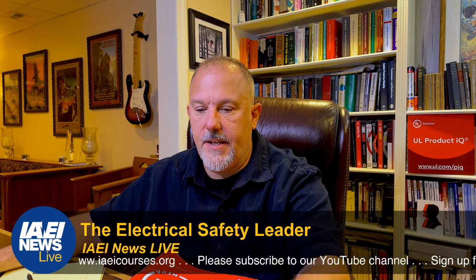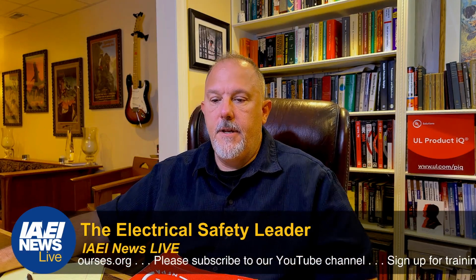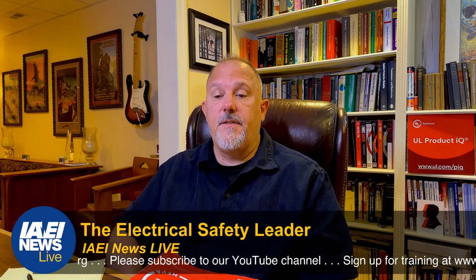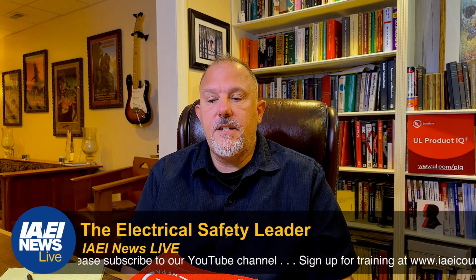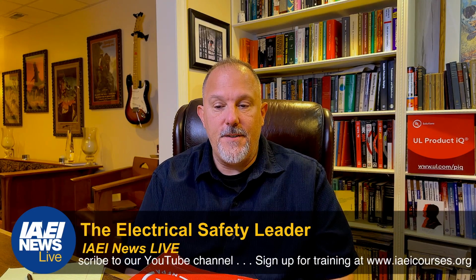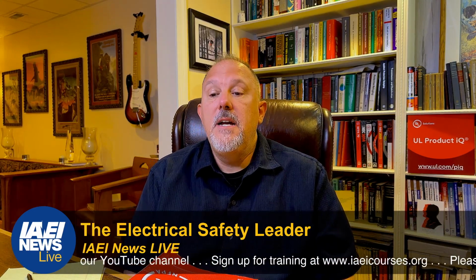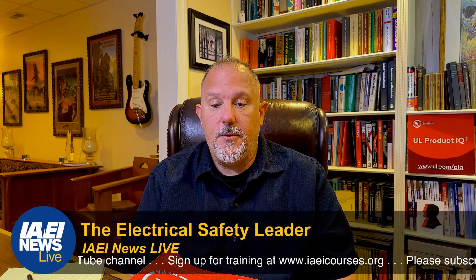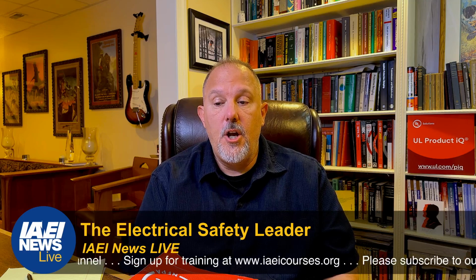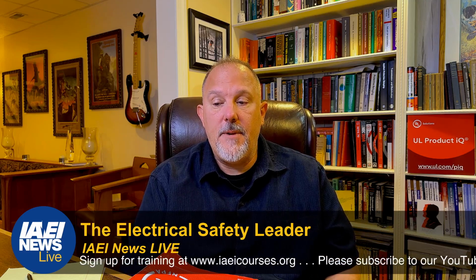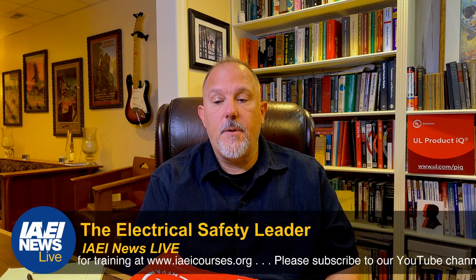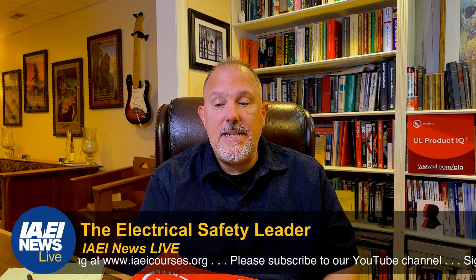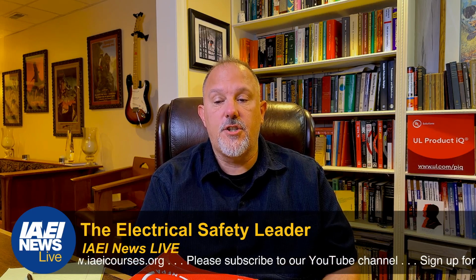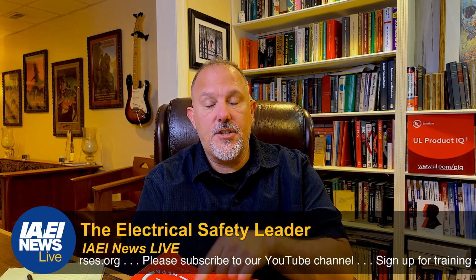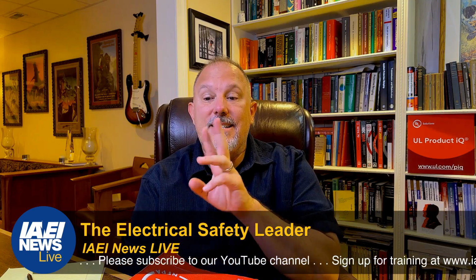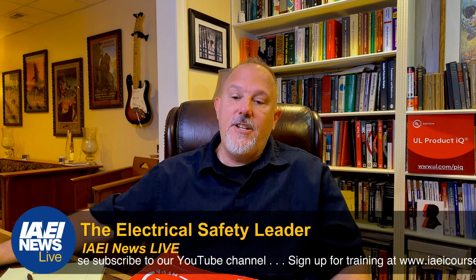Okay, surge protective device. So there's a definition for a surge protective device, an SPD, in the standard. A device composed of at least one nonlinear component. This is different than what's in the NEC. A device composed of at least one nonlinear component and intended for limiting surge voltages on equipment by diverting or limiting surge current, and is capable of repeating these functions as specified. SPDs were previously known as transient voltage surge suppressors or secondary surge arresters. Secondary surge arresters. Interesting.